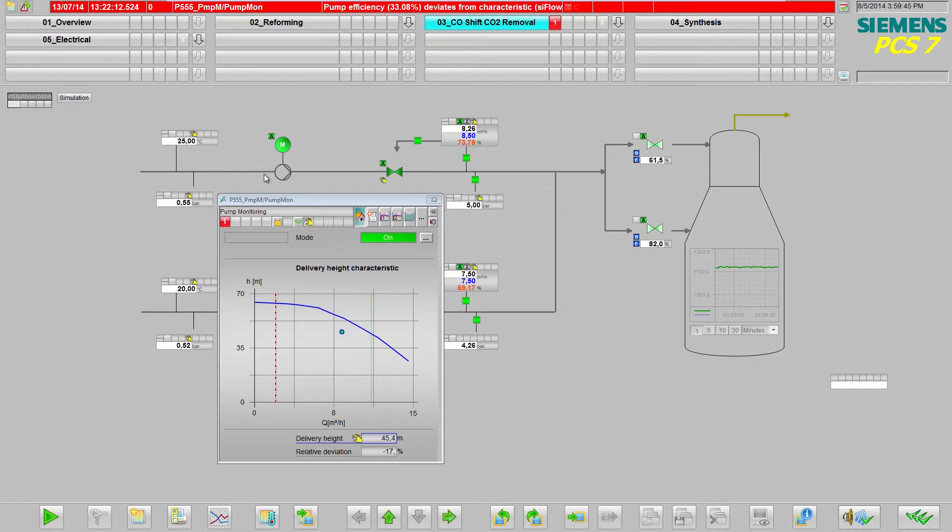In the case of large pumps, this can result in significant financial losses. To put this into figures, if we take a pump that is driven by a frequency controlled motor with 800 kilowatts of power—this is a typical size for some of the larger equipment used in the production of ammonia—a 5% drop in efficiency is equivalent to 350,000 kilowatt hours of energy, or in financial terms, around 50,000 euros wasted each year.